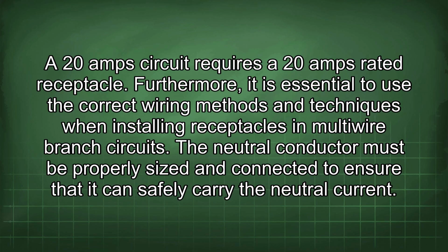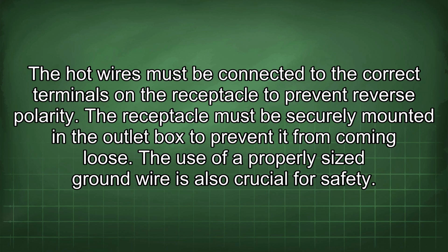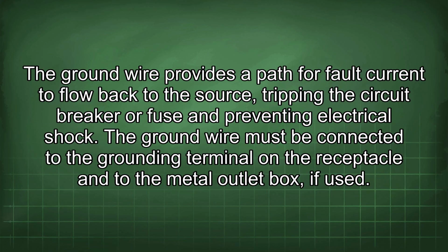Furthermore, it is essential to use the correct wiring methods and techniques when installing receptacles in multiwire branch circuits. The neutral conductor must be properly sized and connected to ensure that it can safely carry the neutral current. The hot wires must be connected to the correct terminals on the receptacle to prevent reverse polarity. The receptacle must be securely mounted in the outlet box to prevent it from coming loose. The use of a properly sized ground wire is also crucial for safety. The ground wire provides a path for fault current to flow back to the source, tripping the circuit breaker or fuse and preventing electrical shock. The ground wire must be connected to the grounding terminal on the receptacle and to the metal outlet box, if used.